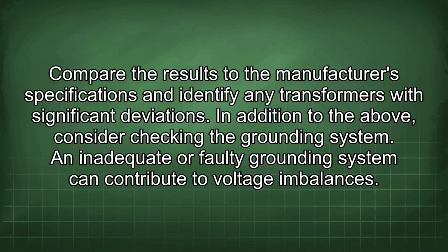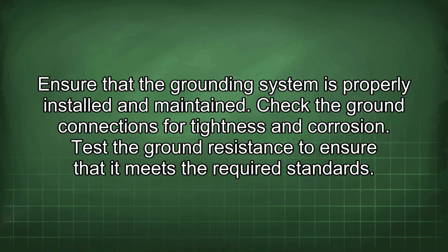In addition to the above, consider checking the grounding system. An inadequate or faulty grounding system can contribute to voltage imbalances. Ensure that the grounding system is properly installed and maintained. Check the ground connections for tightness and corrosion. Test the ground resistance to ensure that it meets the required standards.